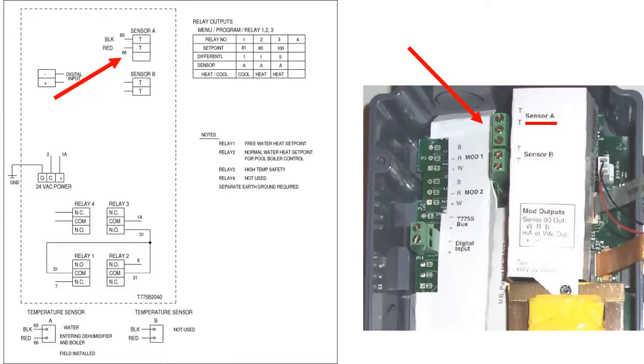The sensor connection is in the upper right corner of the water temperature schematic page. The two sensor wires are connected to the top two terminals of sensor A on the controller. The sensor is to be mounted on the water line entering the boiler and dehumidifier.